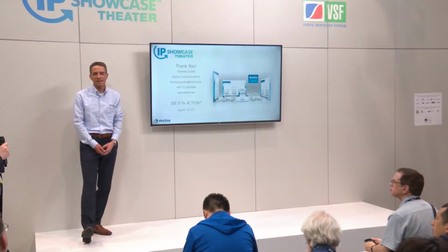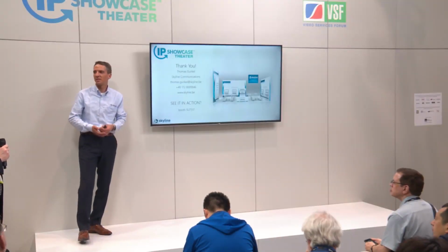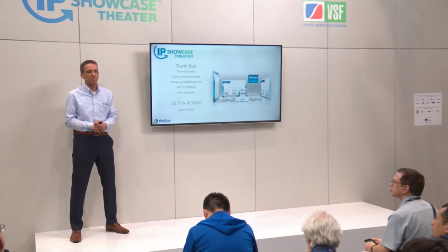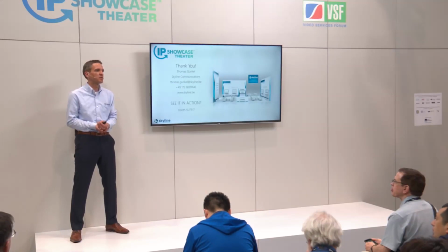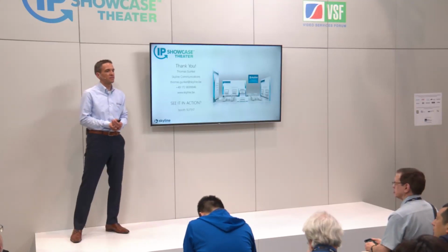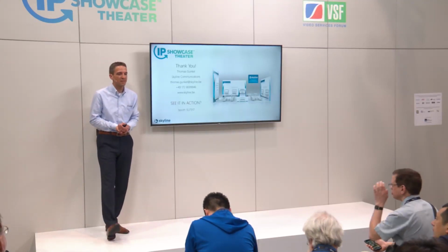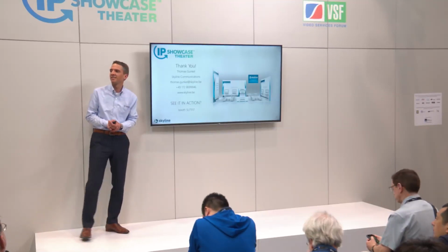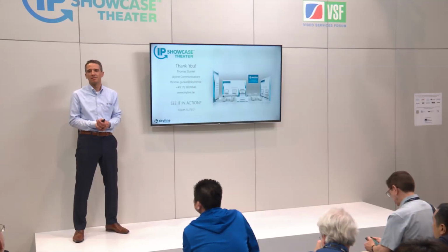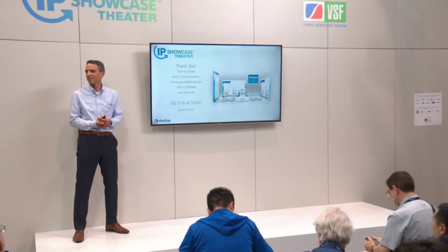The most complex, I might have to ask my engineers, but one we came across recently was that people had a grandmaster which wasn't supposed to be a grandmaster. They didn't realize for a couple of weeks that they were running on a bad grandmaster. And the second problem there was they were running on that grandmaster and also the time was wrong. Timing was set to 1970 or something like that.